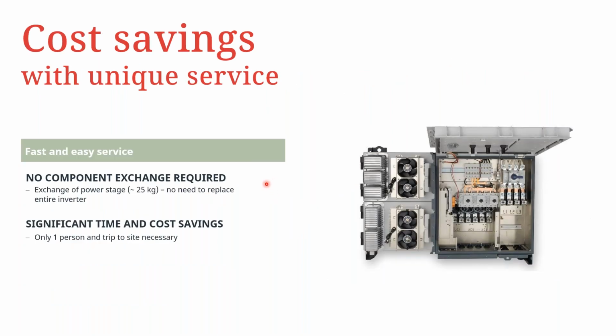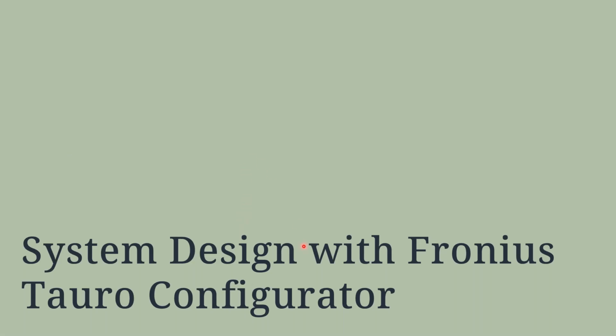So the Tauro inverter also offers the unique advantage as far as service is concerned. Just like the Snap inverters, you can swap a power stage if it becomes faulty. So we can see, for instance, if it's 100 kilowatt, we have 2 power stages, each 50 kilowatt. But for a 50 kilowatt version, we would have only 1 power stage. So if you have to send someone to site for a power stage replacement, only 1 person is enough, and therefore this has quite an effect on the OPEX of the system.